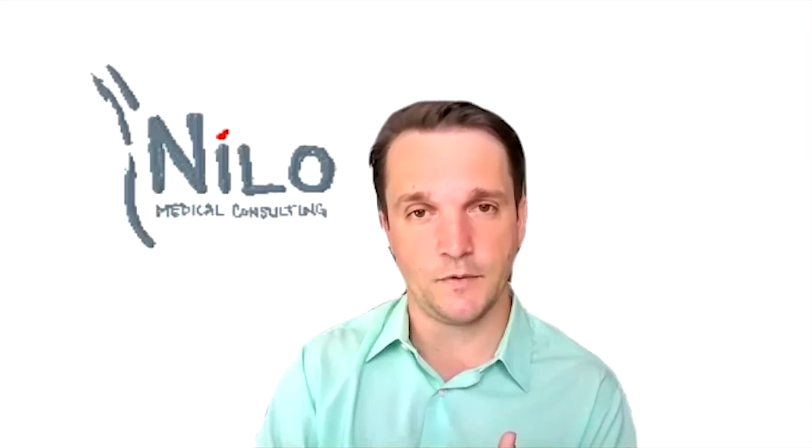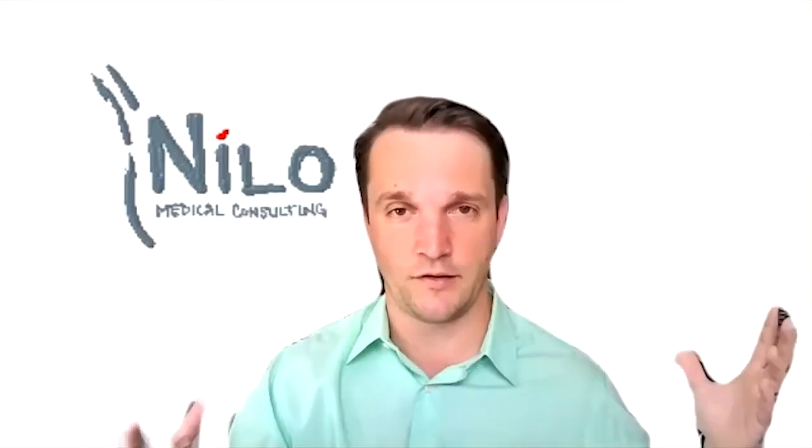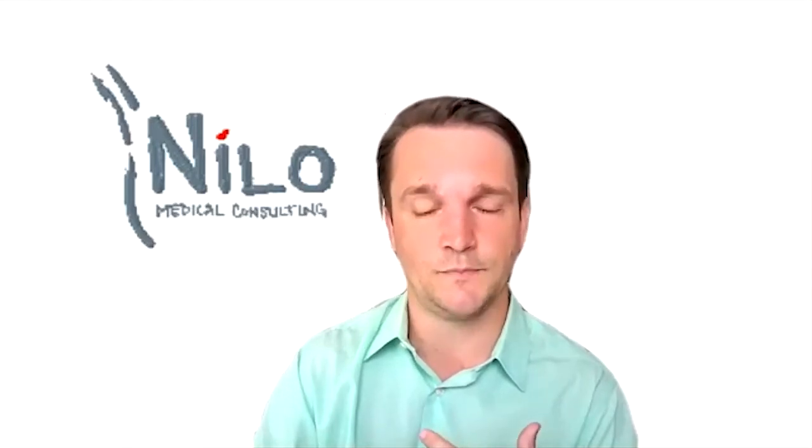The class 3 level is often, to get through at class 3, you need what's called a pre-market approval, which is called a PMA. So that's why PMA is there. And the requirements there are you need to prove individually that your device is safe and effective. And this, for class 3 products, often involves a clinical trial and the full suite of software validation, verification, human factors, cybersecurity, proper labeling. It's basically everything from class 1 to class 2, plus the clinical evidence to demonstrate on its own, not compared to anyone else's, that your device works in a safe and effective way, in a statistically safe and effective way as well. This is the highest level of control.